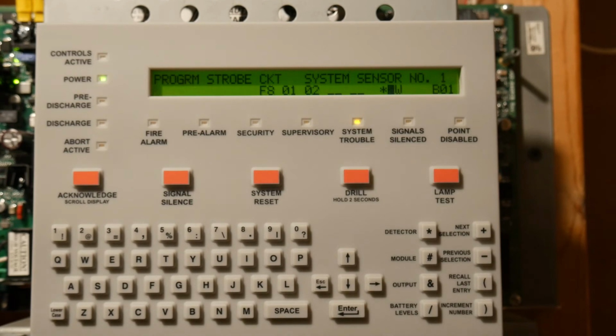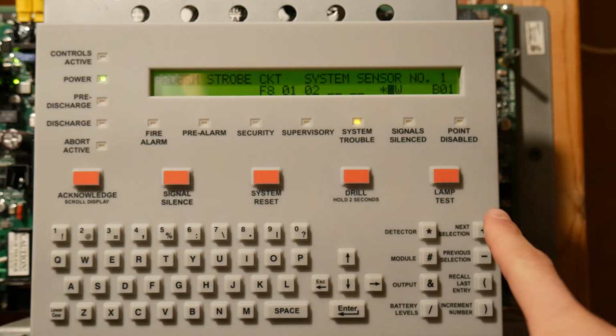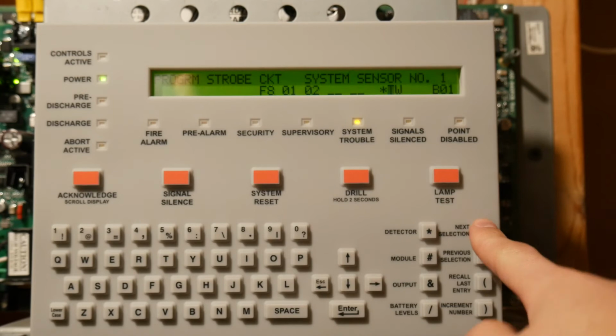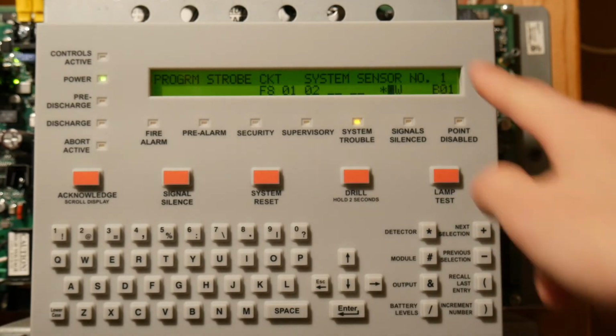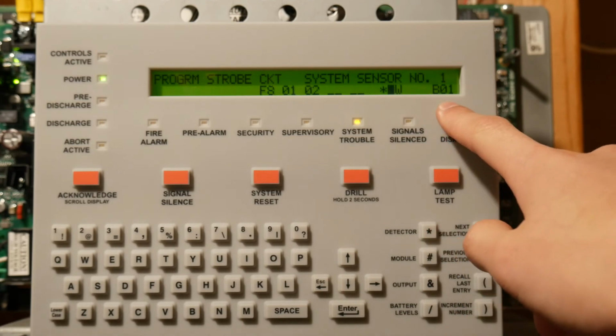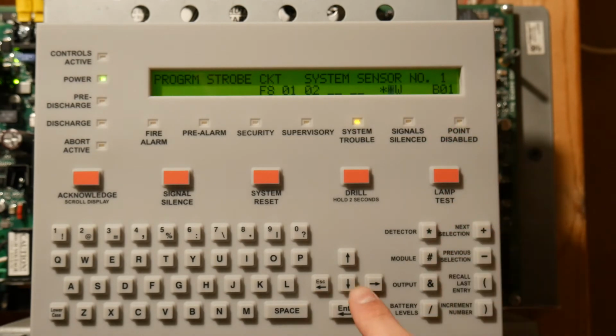Usually you want to set silenceable because you want the strobes to stop flashing as well, because that's the new ADA code requirement. But since this is a hobby system and I want my strobes to flash and my horns to stop, I'm going to set this as a non-silenceable NAC. And B01 stands for Bell Circuit 01.